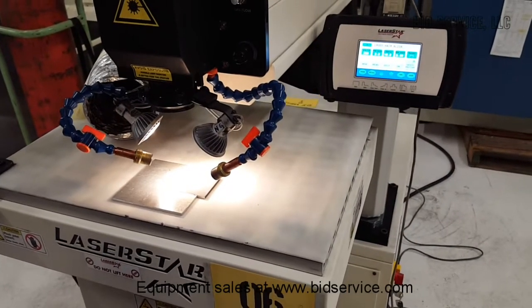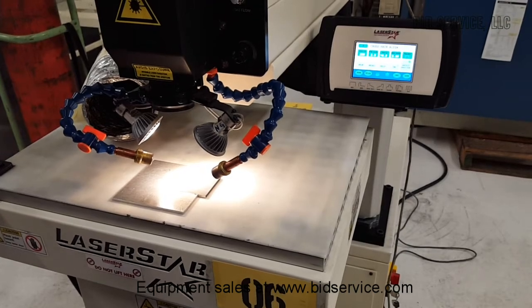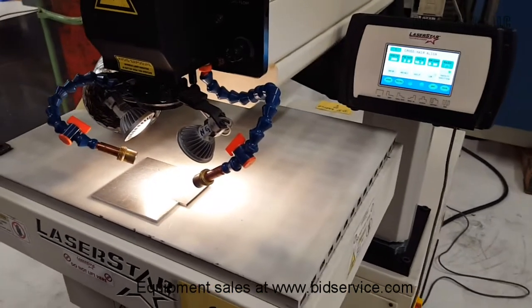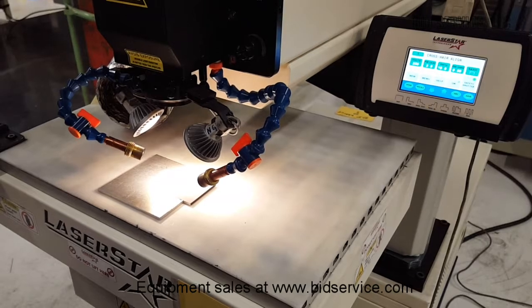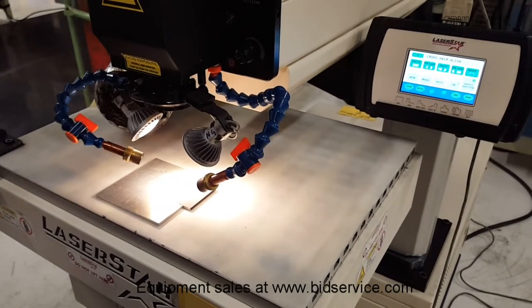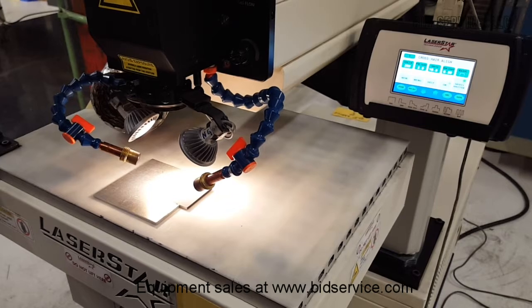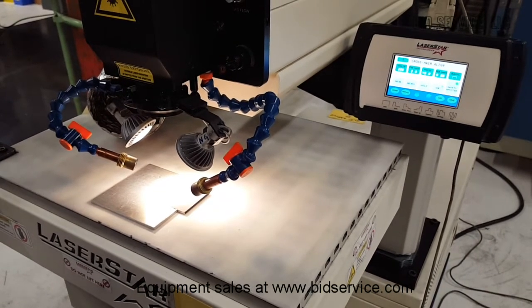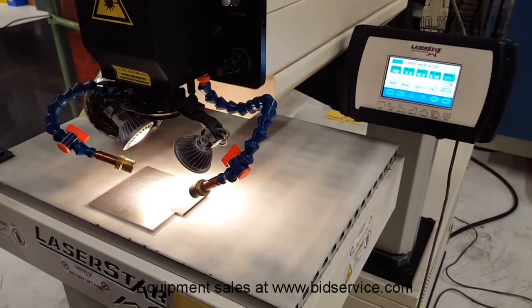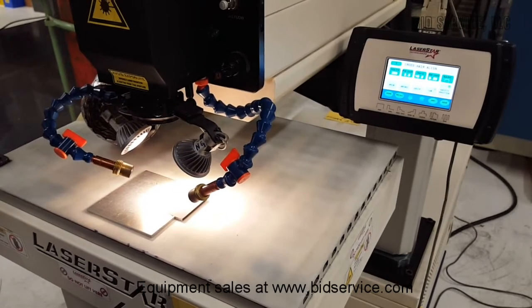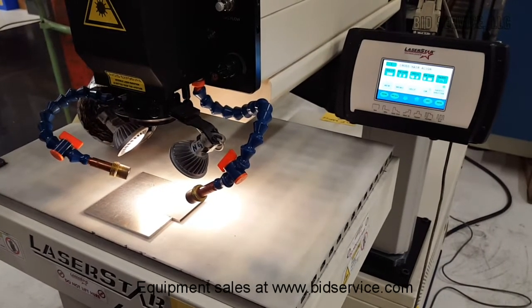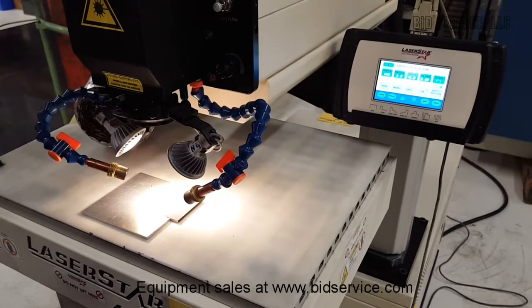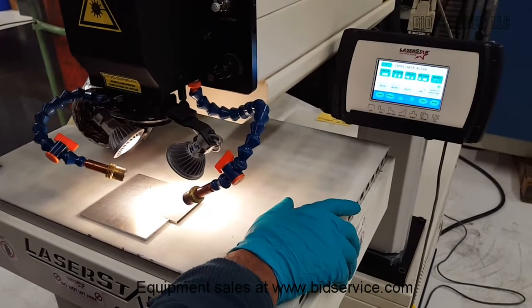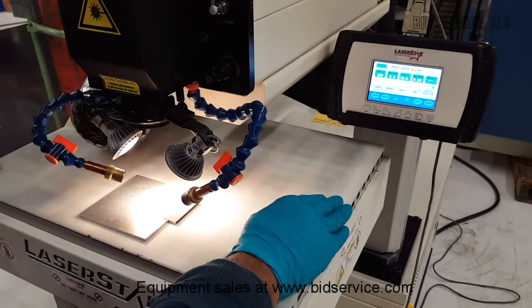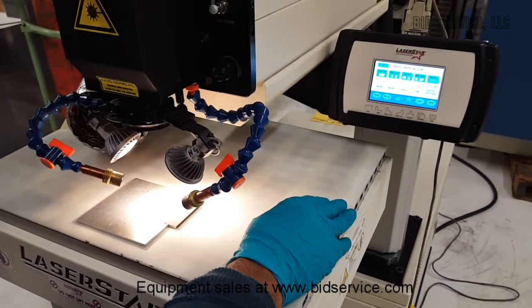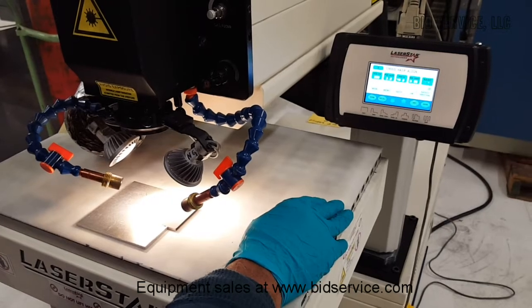Laserstar mold repair system. It has a powerful neodymium YAG laser in it, and it also includes a recirculation water chiller. Only DI water is to be used, and there's a DI water tank which is to be filled slightly above the minimum water level as indicated in the user's manual.